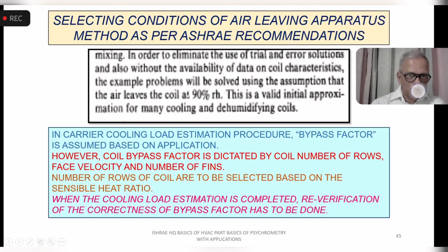Now, as per the ASHRAE recommendations, how do you decide the leaving apparatus condition? That is what we saw a few slides back, 90% RH. In the Carrier cooling load estimation procedure, the bypass factor is assumed based on the application. However, the coil bypass factor is dictated by the coil number of rows, face velocity, and number of fins. The number of rows of the coil is to be selected based on the sensible heat ratio. When the cooling load estimation is done, a re-verification of the correctness of the bypass factor has to be done, but this rarely happens in reality.